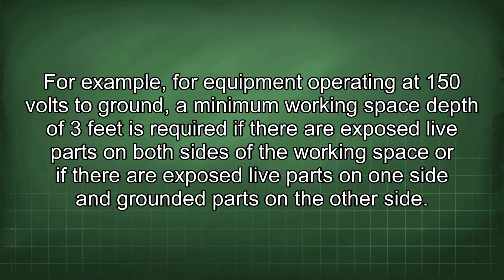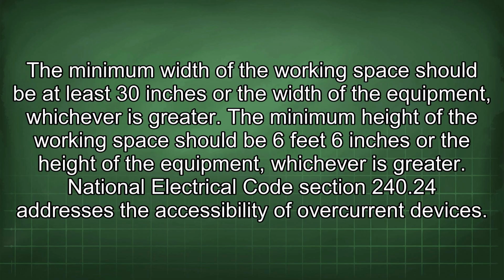For example, for equipment operating at 150 volts to ground, a minimum working space depth of 3 feet is required if there are exposed live parts on both sides of the working space, or if there are exposed live parts on one side and grounded parts on the other side. The minimum width of the working space should be at least 30 inches or the width of the equipment, whichever is greater. The minimum height of the working space should be 6 feet 6 inches or the height of the equipment, whichever is greater. National Electrical Code Section 240.24 addresses the accessibility of overcurrent devices.